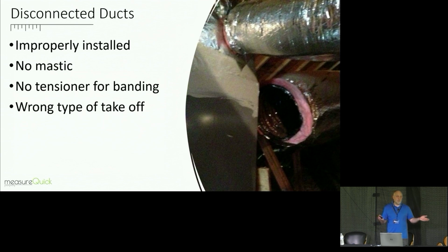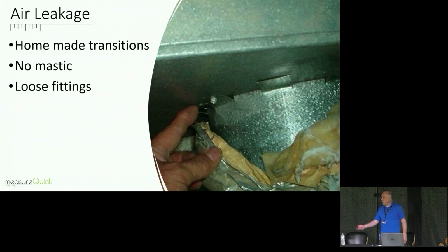What would happen to your suction pressure? If you had a return duct leak, you're pulling in hot air from an attic. Suction pressure would go way up. How about your temperature split? What would your temperature split do? Temperature split's going to go way down, right? So there's about 6, 10 things that MeasureQuick picks up, looking at all these relationships, that's going to see that problem. But if you dismiss that problem, you're dismissing an opportunity, right?